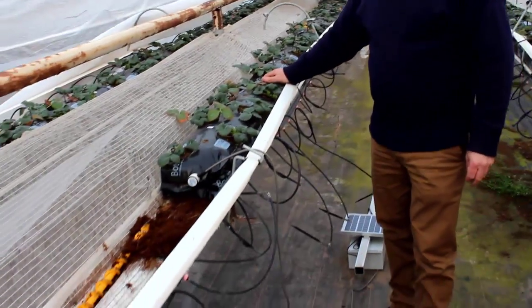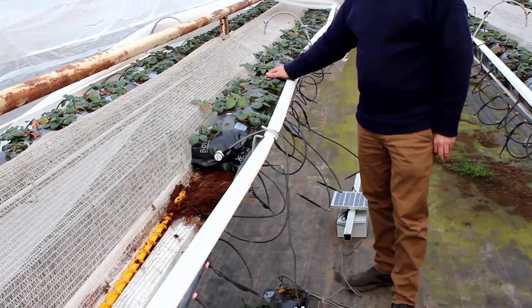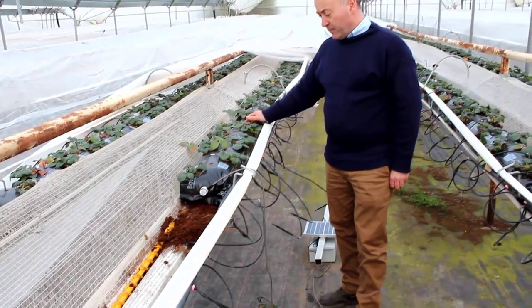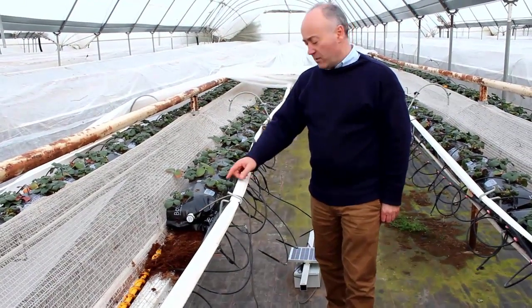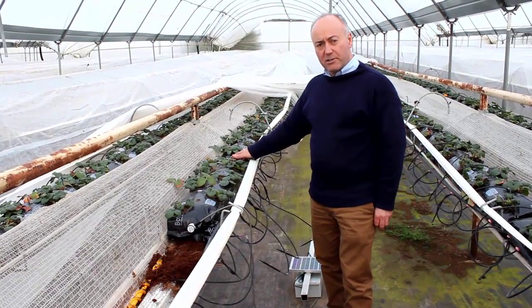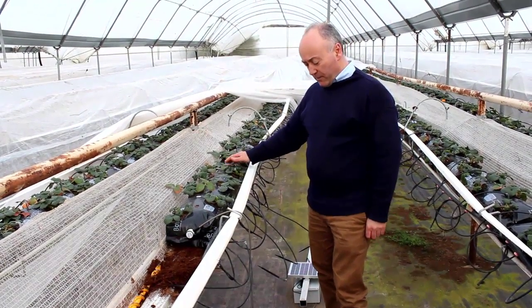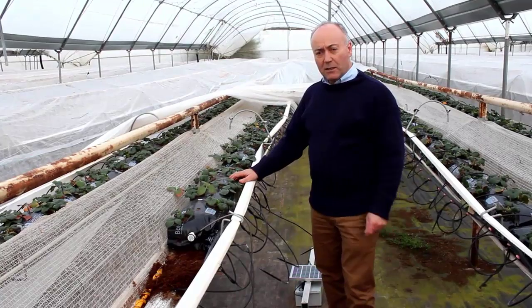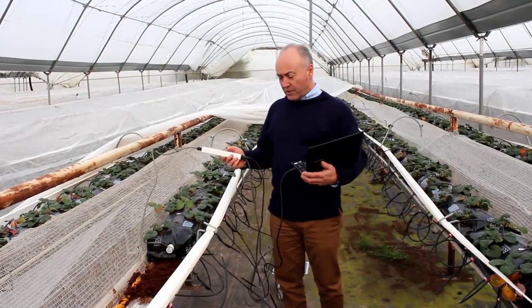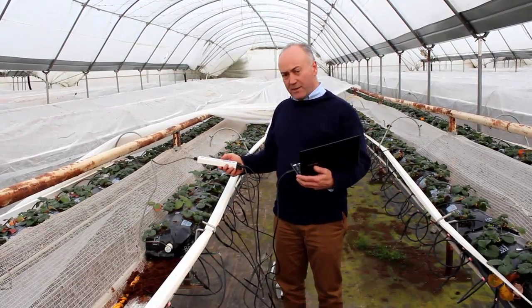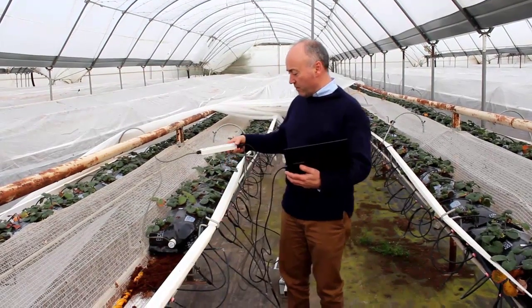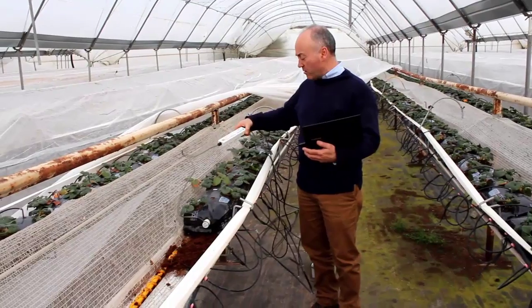So the next thing that we need to do, just like you saw in the film installing the probe into the pot, we need to now connect to it, make sure all these sensors are giving us good readings to ensure the install is correct. Once we've done that, we can tidy the cables up and leave everything in situ. So with these probes, the electronics are separate from the probe now, which makes it actually easier once you've installed, because we can work on the electronics well away from the probe.